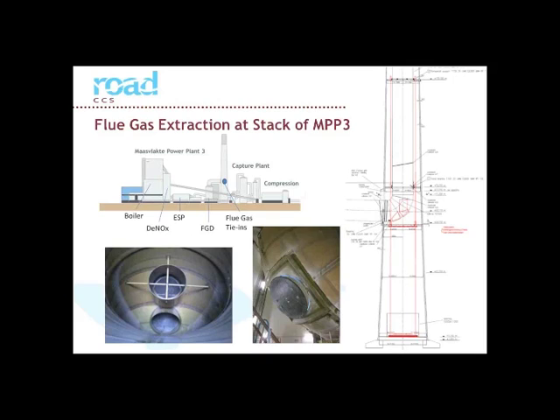The tie-in point can be found inside the concrete stack of MPP3. I will try to point it over here, at 60 meters high in the chimney. There the GRP duct, the flue gas duct, makes a 90 degrees turn, and two nozzles were installed. You can see them at the right side in red. Both 3.8 meters diameter, one for the extraction of flue gas from the power plant, and one for the return of the flue gas that is treated in the capture plant. Later on, the ducts to and from the capture plant will be connected here and run inside the stack to an opening at the ground level.